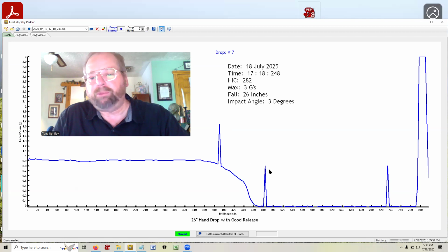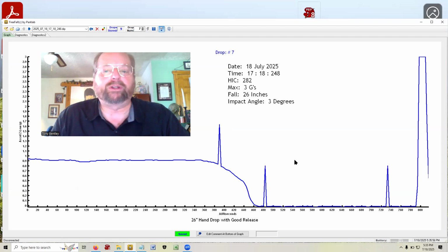Now these 3 points here are artificial. They're not what the sensor actually measured. They're put in there as markers. This first marker indicates, okay, this is where we've detected that we're beginning into free fall. We're starting to fall. And it calculates the time from the initiation of free fall to the impact, and it uses that time to calculate the fall height.